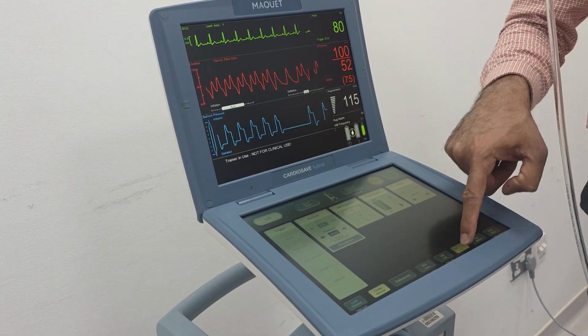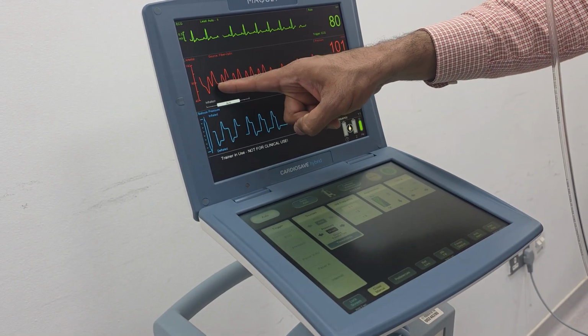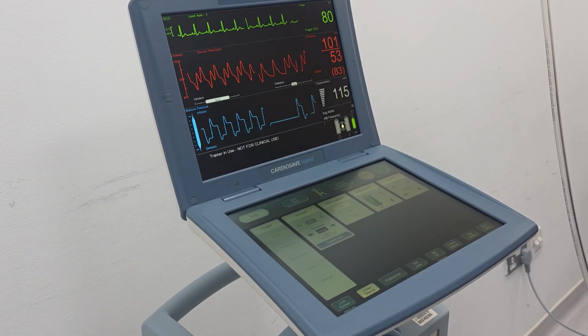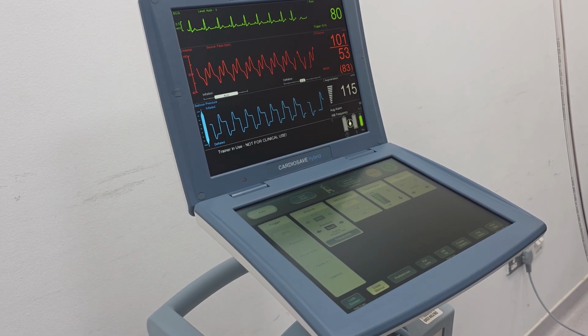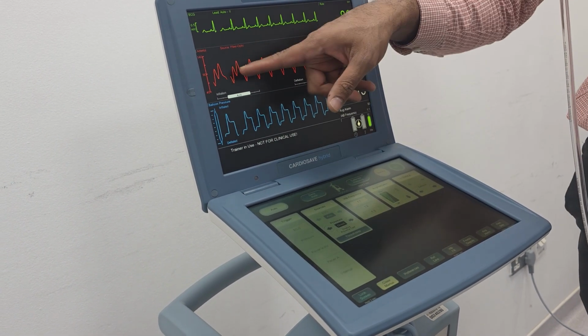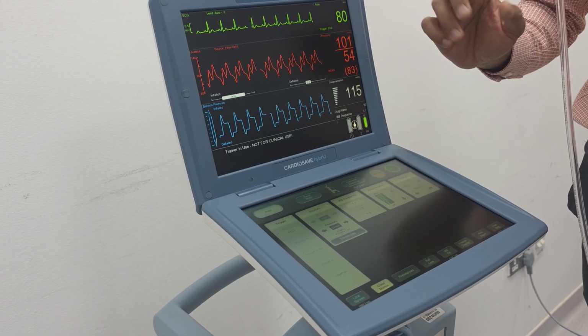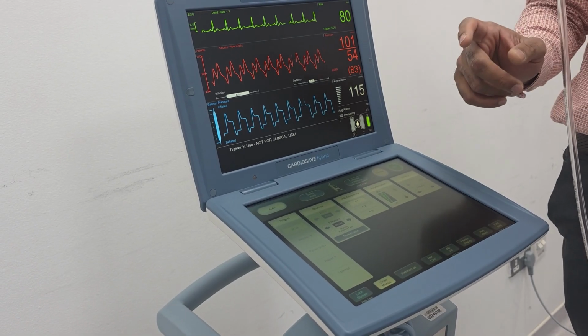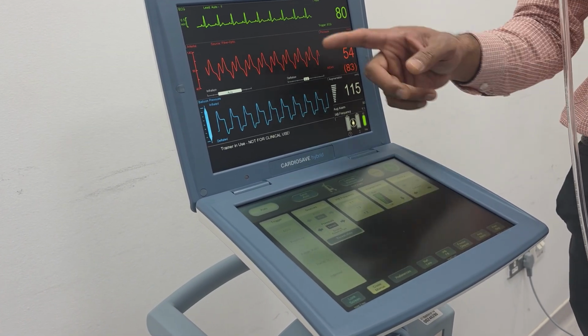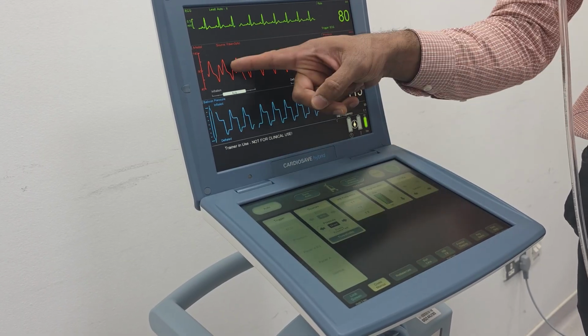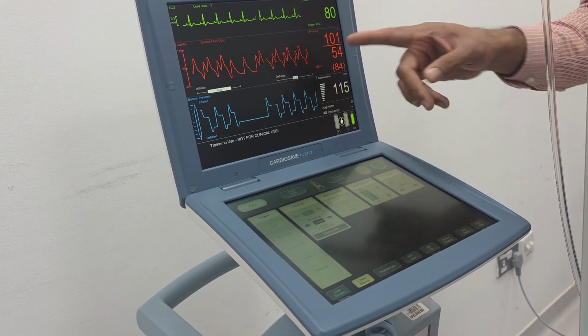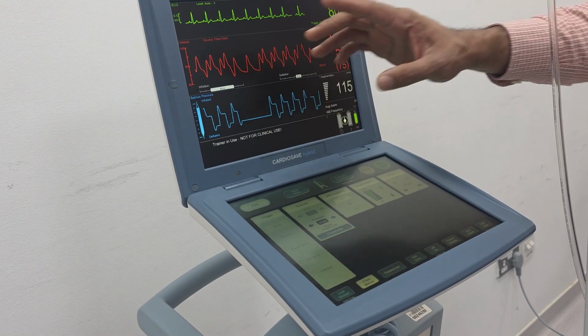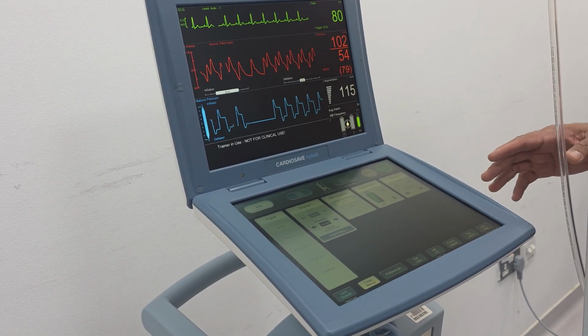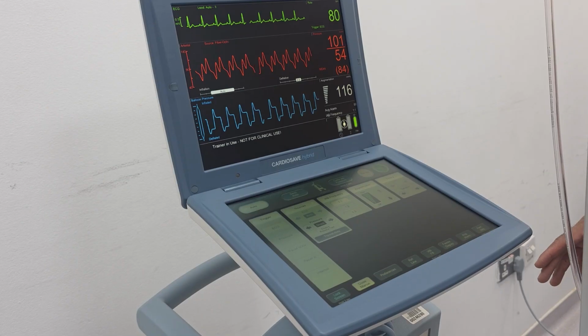Okay, I'll just unfreeze it. Now you can see there shouldn't be any dicrotic notch problem. It's adjusted automatically, which is called auto updation based on the pressure waveform. Okay, that's it. It is checking the dicrotic notch position every 15 seconds initially. After that, every 2 minutes, it will check the dicrotic notch, same like CS300. Just for information, you cannot see the missing 2 beats. So it's very common. Okay, the machine is checking the dicrotic notch position and adjusting automatically.